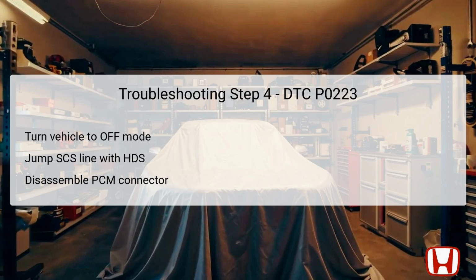If continuity is confirmed, this suggests that the THL2 wire is functional, and further investigation into authorized service information or substituting a known good PCM is warranted. Conversely, if continuity is not detected, an open circuit in the THL2 wire needs to be repaired.